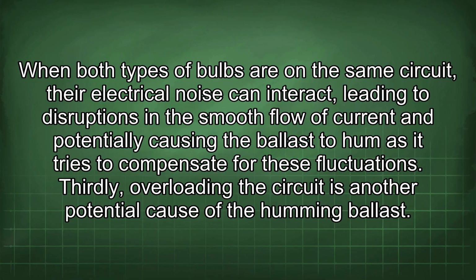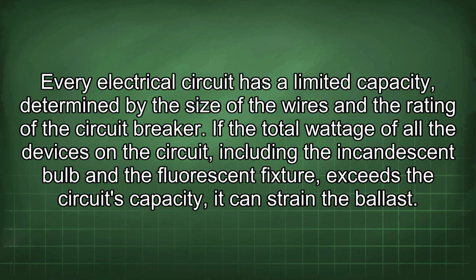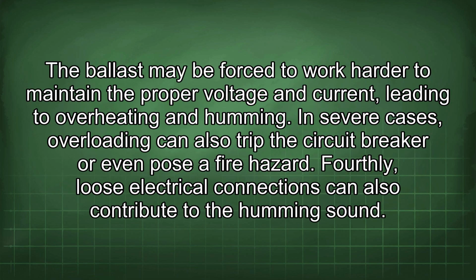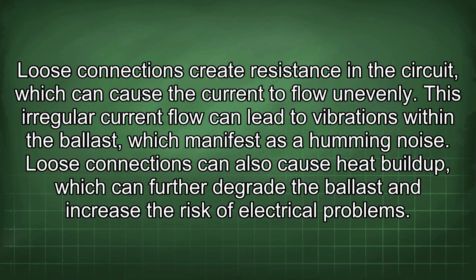Thirdly, overloading the circuit is another potential cause of the humming ballast. Every electrical circuit has a limited capacity determined by the size of the wires and the rating of the circuit breaker. If the total wattage of all the devices on the circuit, including the incandescent bulb and the fluorescent fixture, exceeds the circuit's capacity, it can strain the ballast. The ballast may be forced to work harder to maintain the proper voltage and current, leading to overheating and humming. In severe cases, overloading can also trip the circuit breaker or even pose a fire hazard. Fourthly, loose electrical connections can also contribute to the humming sound. Loose connections create a resistance in the circuit, which can cause the current to flow unevenly.